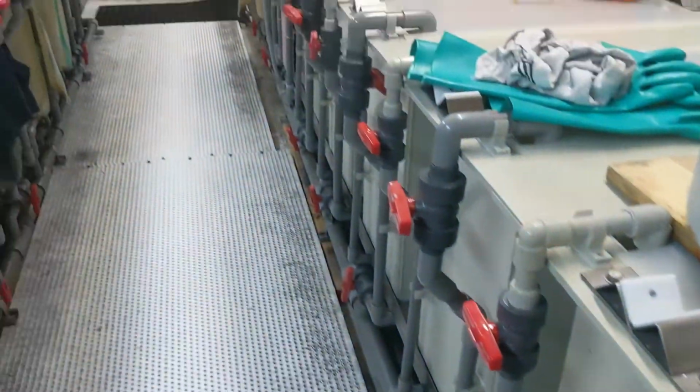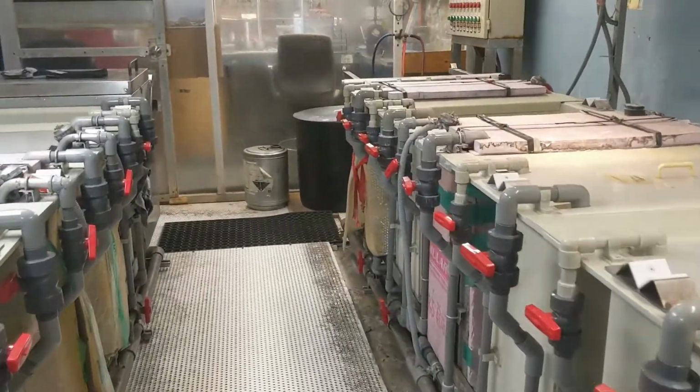Our first job was at a metal anodizing and plating place. They've got a bunch of different tanks of liquids. I know nothing about them. I think there's probably an acid bath or an alcohol bath. One of them has to be cooled to 16 degrees Celsius, which is actually pretty warm. So in order to achieve this temperature, they've created a stainless steel coil. They've used a condenser for like a mini split system, like an air conditioner, to achieve this 16 degrees.